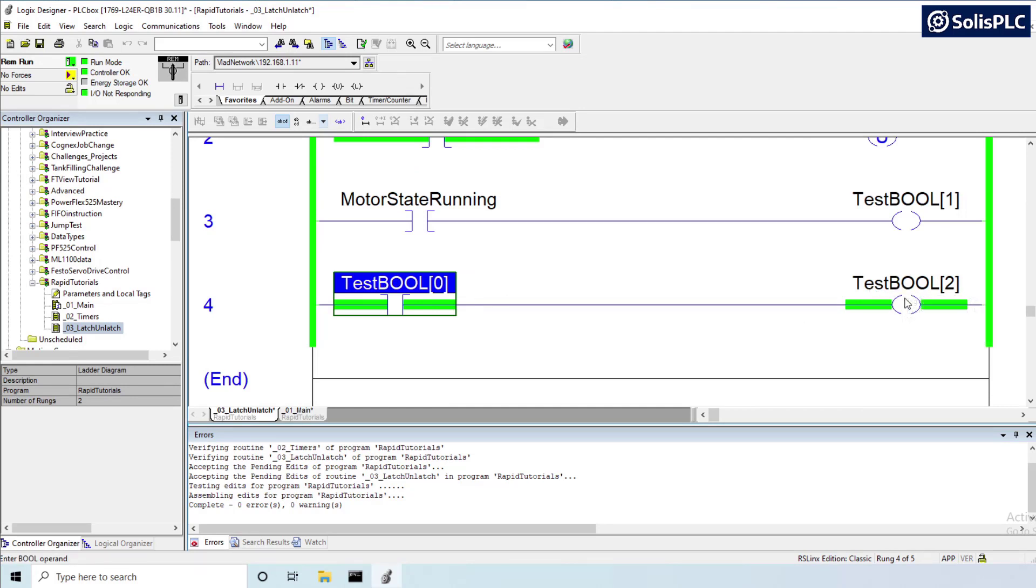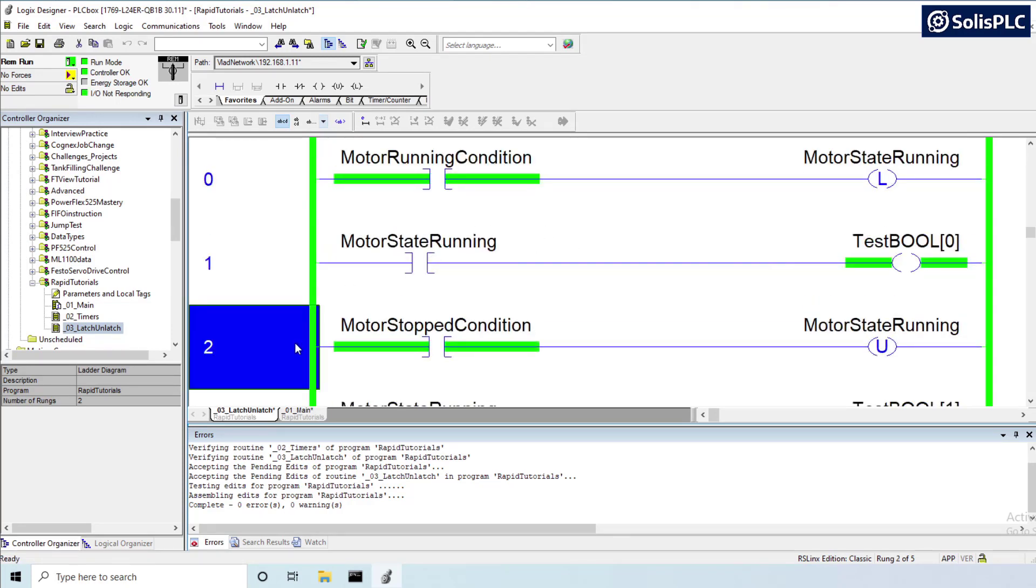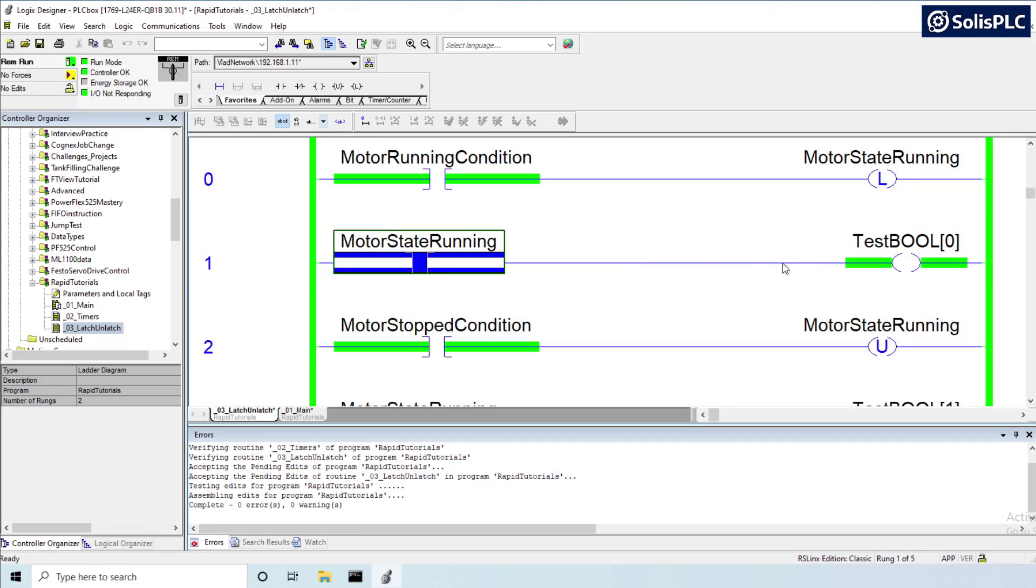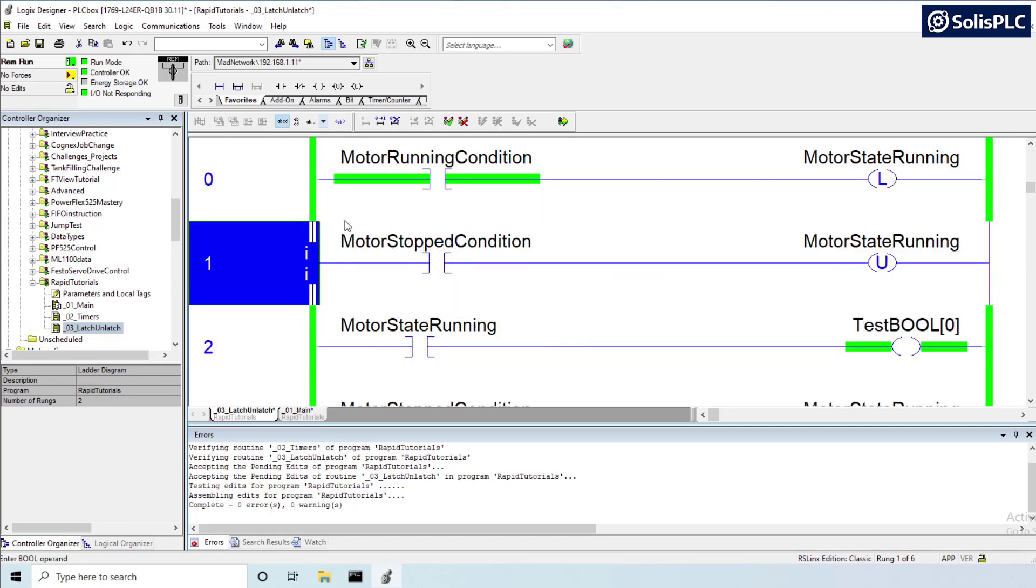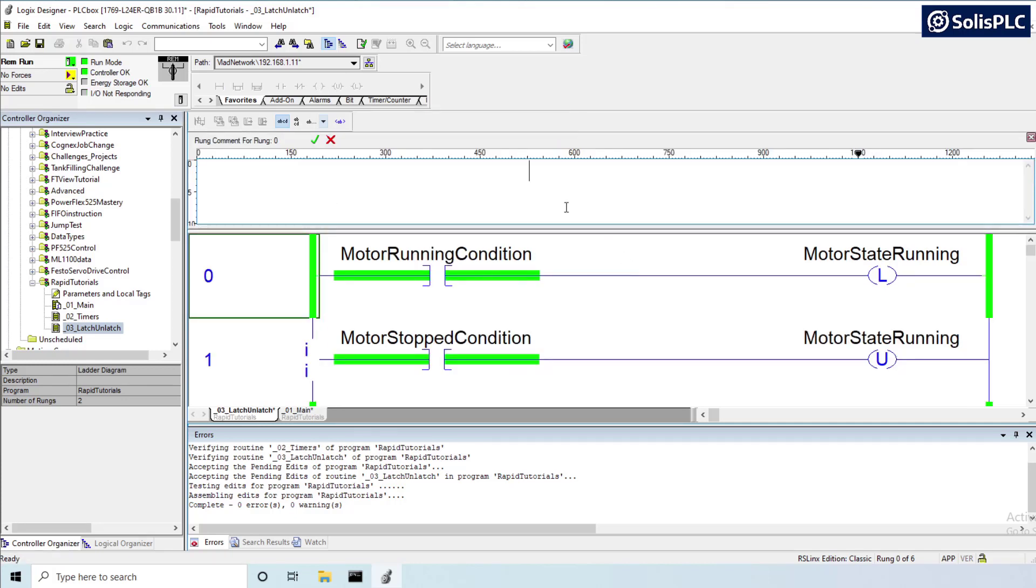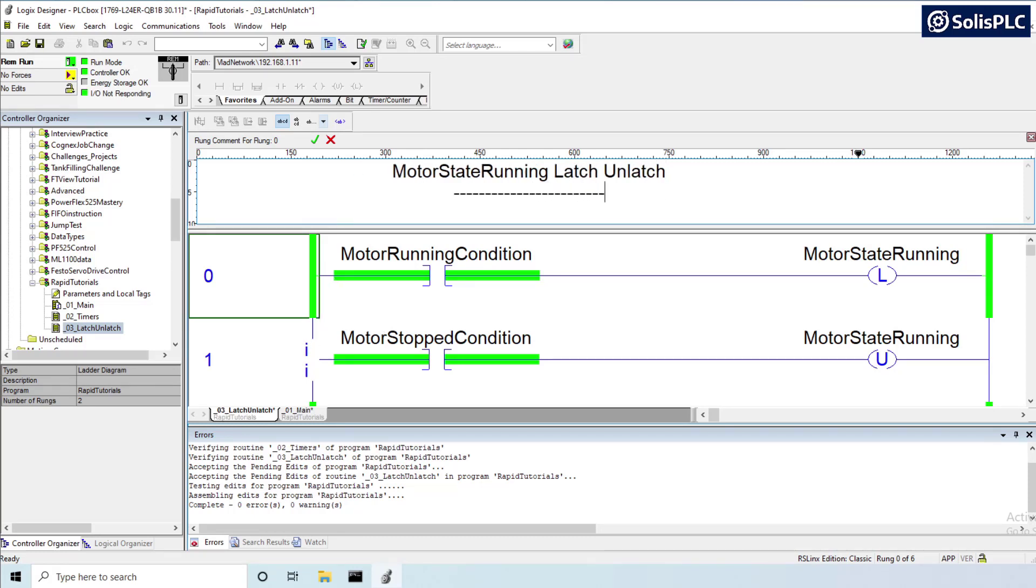This is a very common problem with these latches and unlatches. What I always recommend is first of all never to check logic if you absolutely must use latch and unlatch, never to test your logic in between the two states. What I mean by that is that this rung should always be right next to this latch and I would usually explicitly mention this so this is going to be motor state running latch unlatch in the comments.